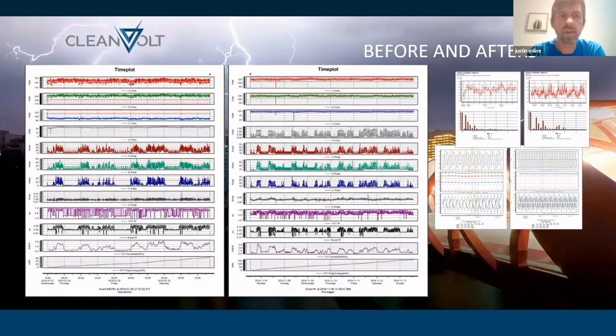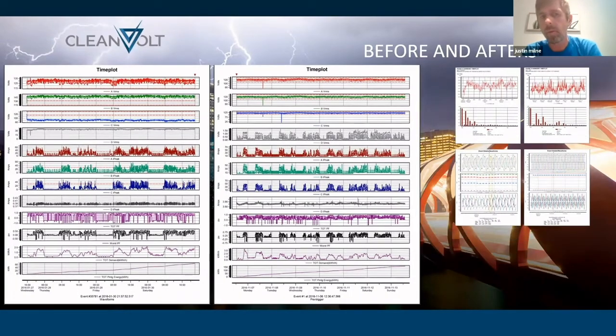This is a time plot for the same test. I'll draw your attention down to the neutral on the right-hand side. It's the fourth one down that's gray. Typically, when you're doing this time plot, that neutral should show a straight line on 0. But as you can see, the range is 0 to 1.5 volts. And you can tell that the neutral's trying to jump up. That should be a straight line at 0, but because that wiring condition is still there, you can see the neutral energy trying to jump up.